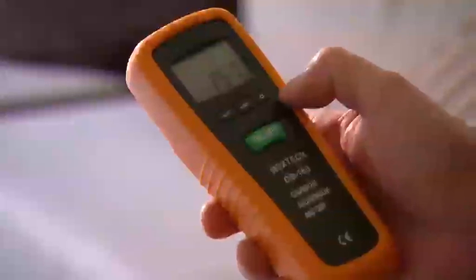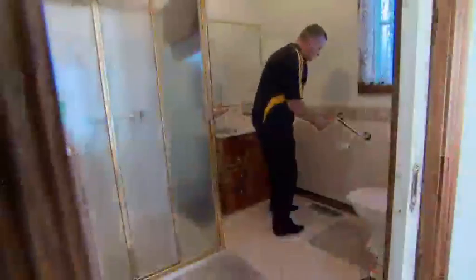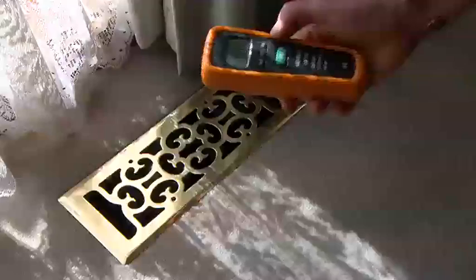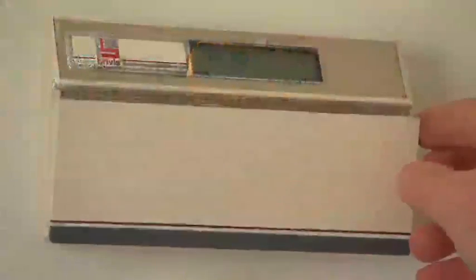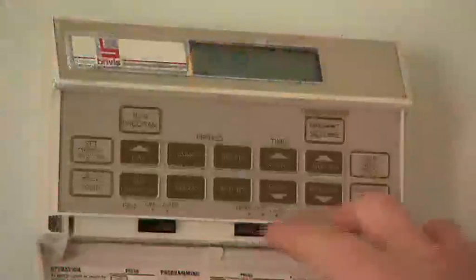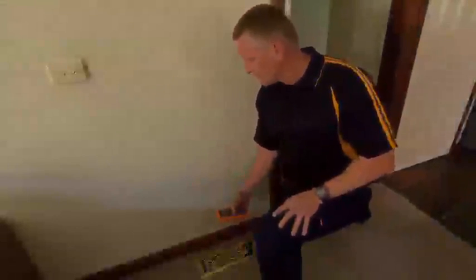Ensure all indoor gas appliances are not operating. Carry out a safety inspection of the appliance. Turn on your detection equipment and take a background reading in separate locations within the building, as the problem may be caused by a separate source and not the gas appliance. Light the gas and operate with the burner and fan, if fitted, on the higher setting. Place the detection equipment sampling probe in the airstream of the nearest duct outlet, floor register or ceiling register. Monitor for CO for a further 10 minutes.